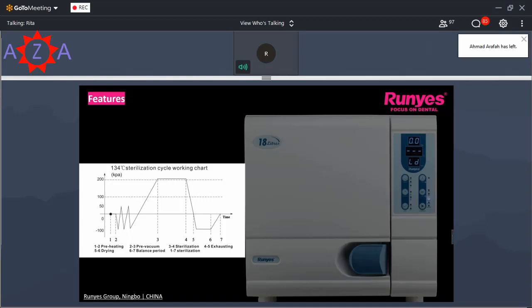And we also have emergency pressure release ports fitted with a safety valve at the backside of the autoclave. From this chart, you can see for 134, the certain pressure is 2.1 bar, but in case the pressure reaches 2.7 bar due to some emergency, the safety valve will automatically open to release the pressure to ensure safety. This is very unique to ensure the reliability and the safety of the autoclave.